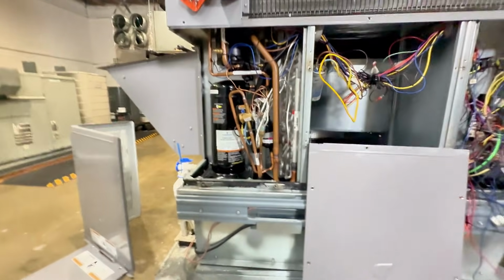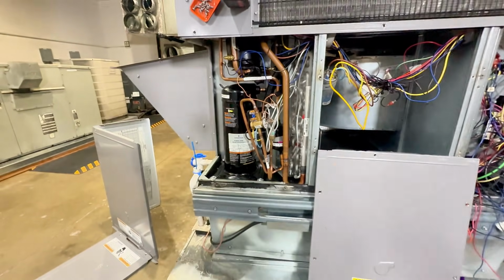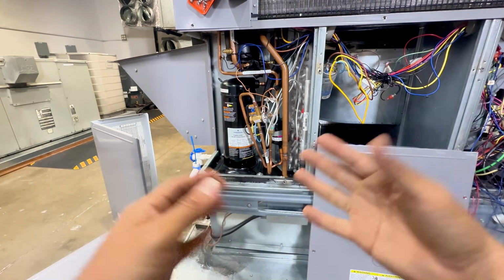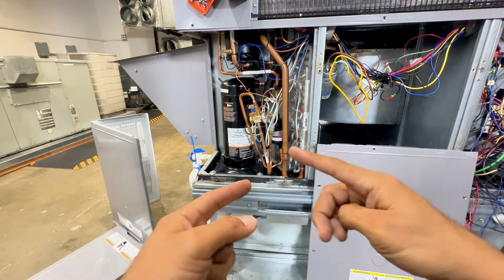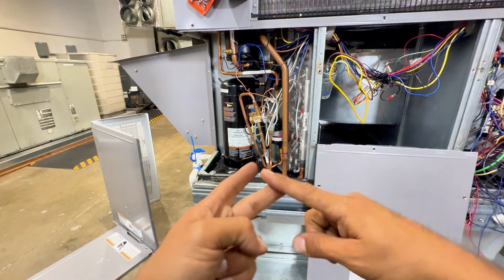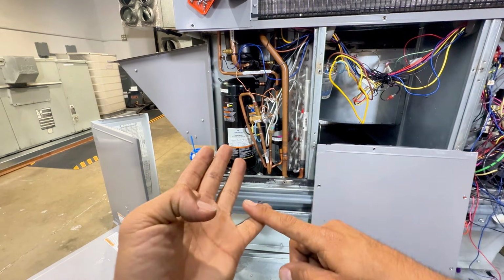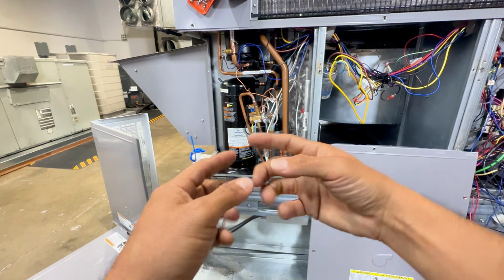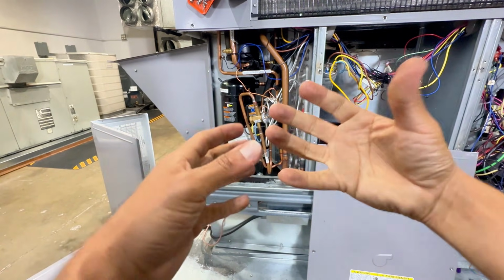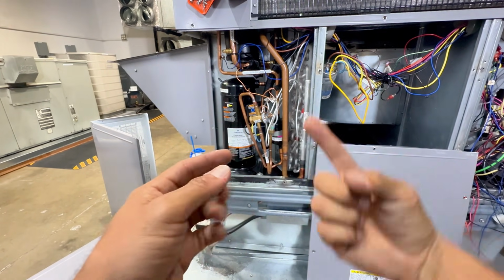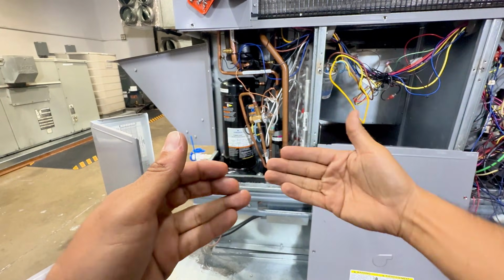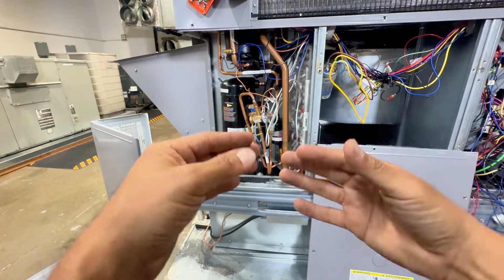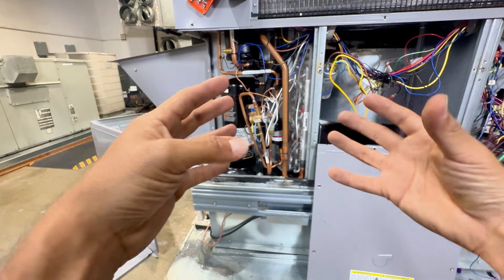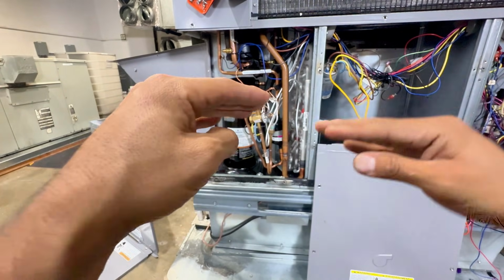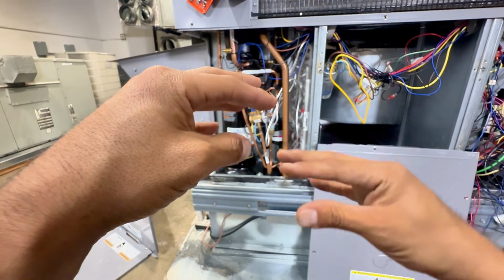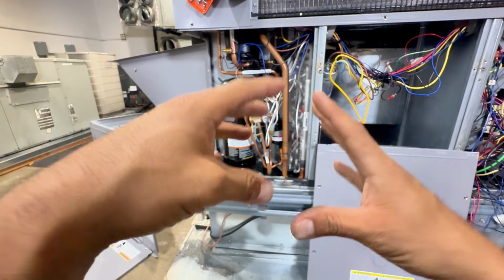Now, have in mind though, this is important. It does say it's 14. But that 14 can change due to a lot of things. If you have a dirty filter, a dirty condenser, if you're undercharged, if you're overcharged, guess what? If you're overcharged, that compressor is doing more work, and that current is going to go up. And if it exceeds that 14, that's not good. Even under heavy load, if everything is clean with good airflow, it'll be close to 14. And even if you're not that close, it should be somewhere around that ballpark.